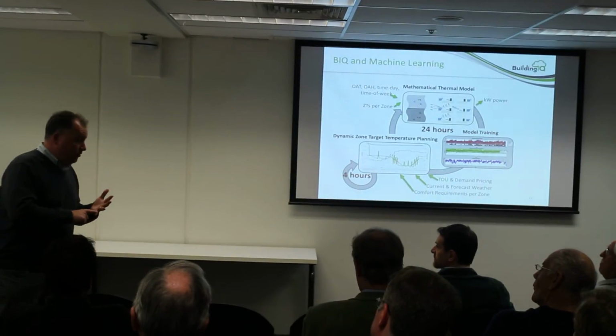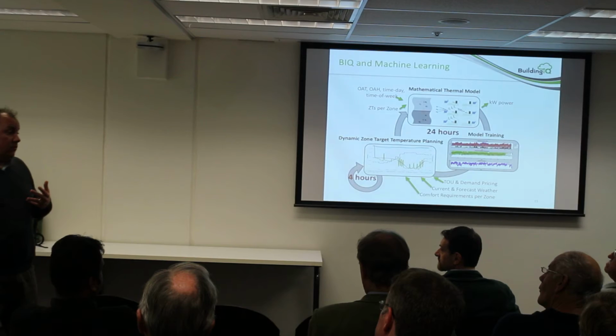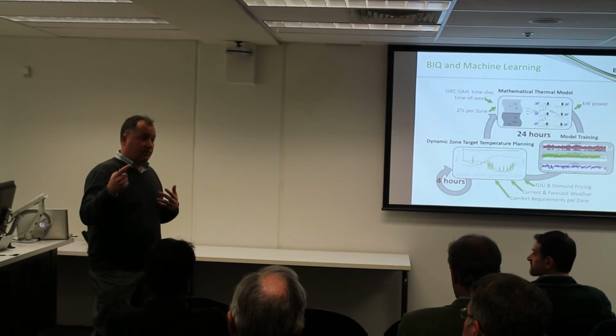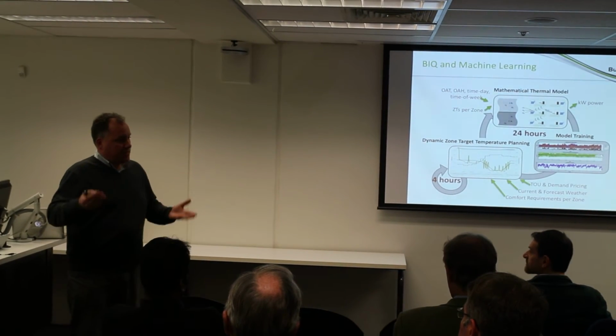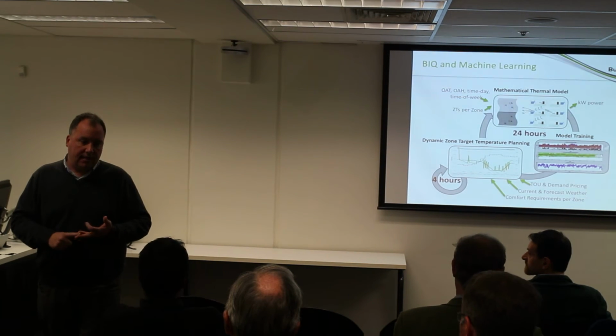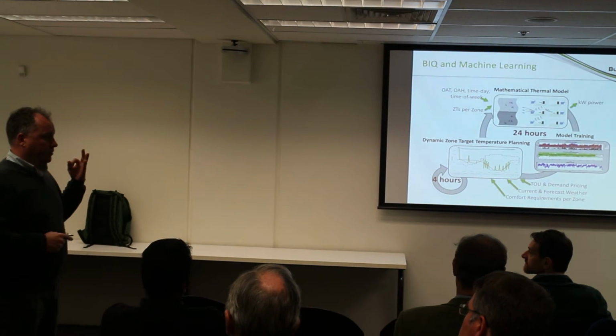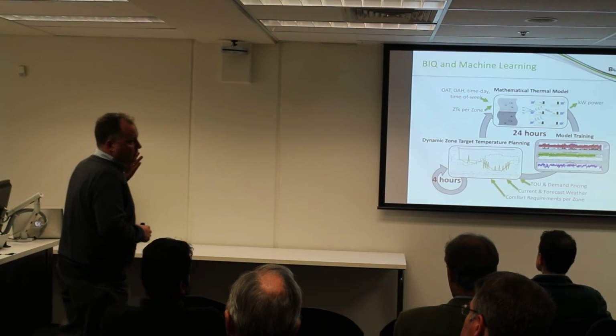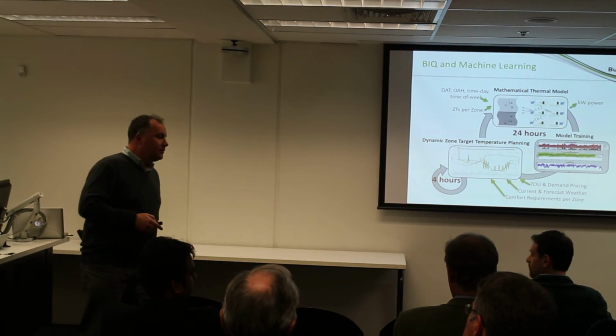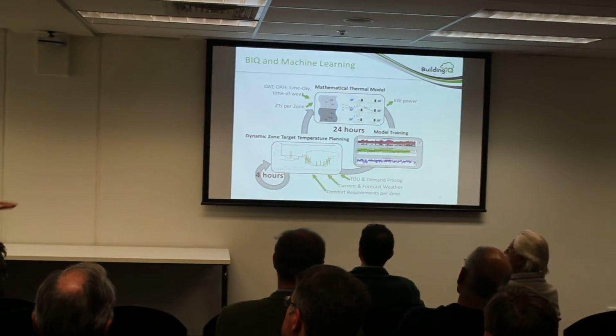We take in the power, we take the inside temperature, so we build up a model by measuring the actual space for about 30 to 60 days. Then we take the outside air temperature and create a relationship between those three things. And that's a thermal model. Yeah, it's simple, and it works.